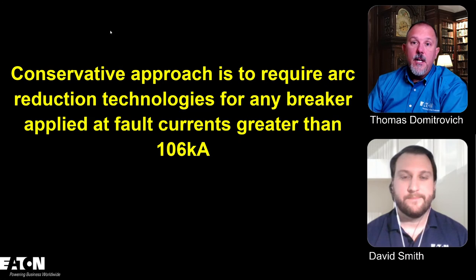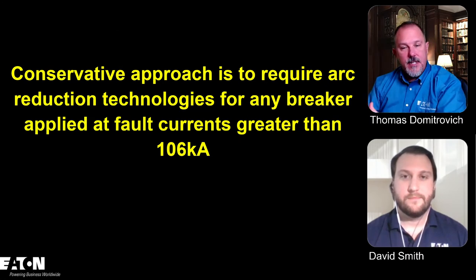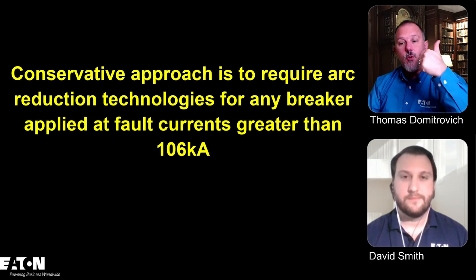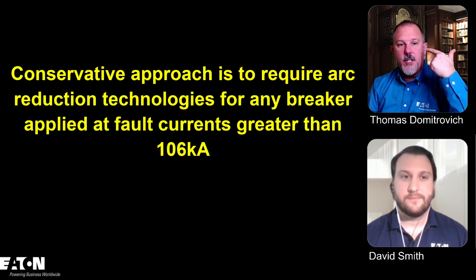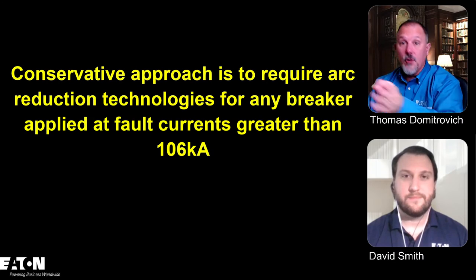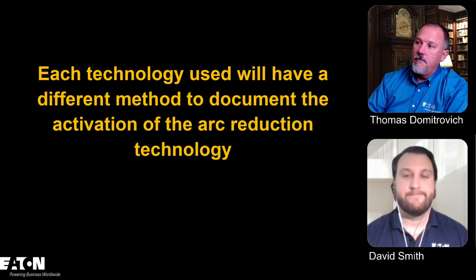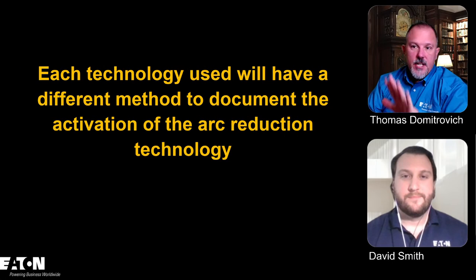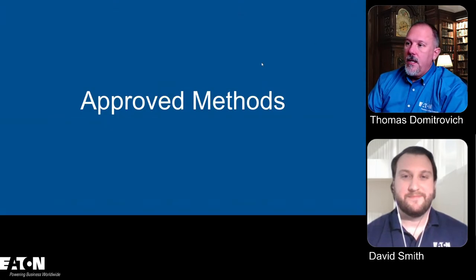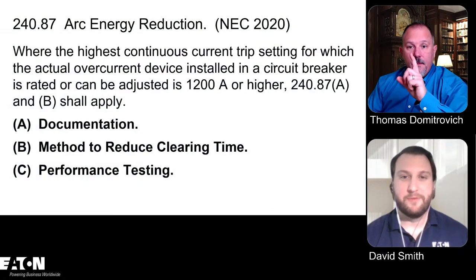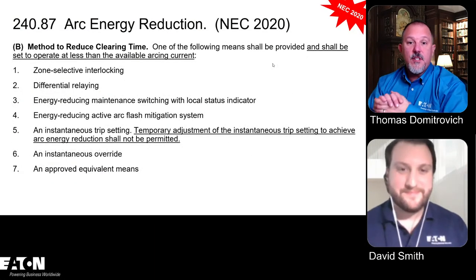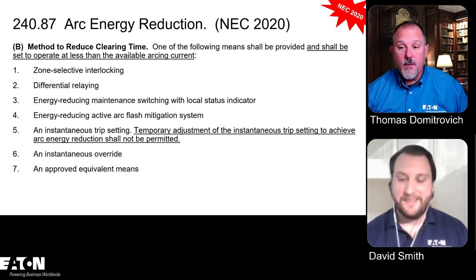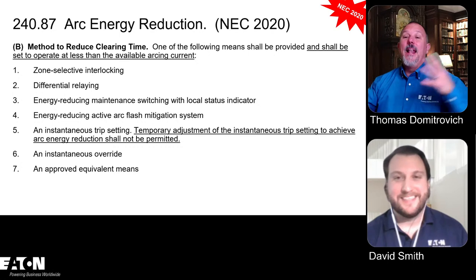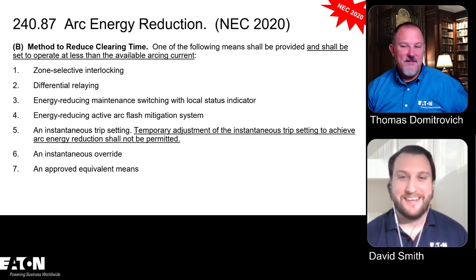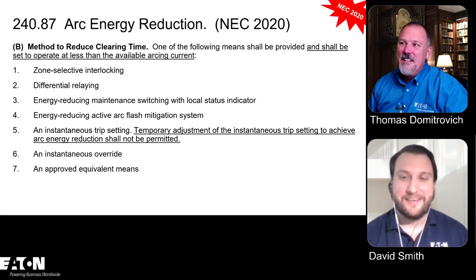Exactly. So, if your arcing currents at 106,000 amps are in the instantaneous region or in the zone selective interlocking region and all that good stuff, then you're going to be there at 150,000 amps or 200,000 amps. So each technology is going to have a different method to do that. All right, approved methods. Yep, now we're into approved methods, and there's seven options for you. The seventh option is an approved equivalent means. A plethora. Just a plethora. An embarrassment of riches that we have here at 240.87 of the 2020 edition of the National Electrical Code.